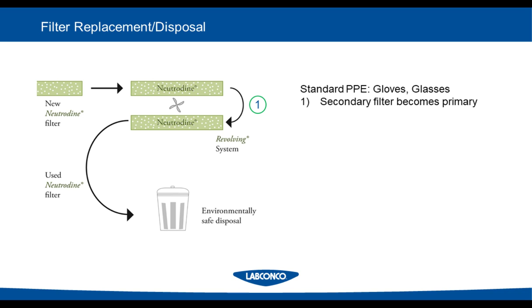So you would then take the secondary filter, the one that's on top, the safety filter, move it down to the primary position so it can start doing all the heavy lifting, as I call it. Step 2, you put a new secondary filter on top. Step 3, you package the old primary filter in the heavy poly bag and cardboard box that the new filter came in, and send that off for environmental disposal.